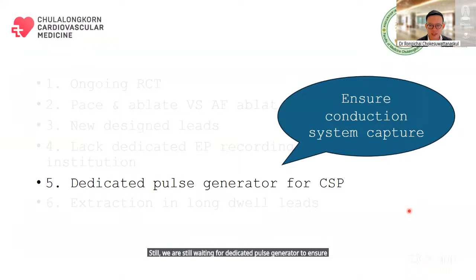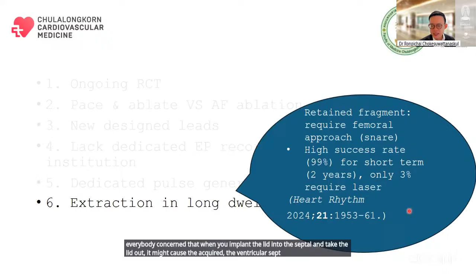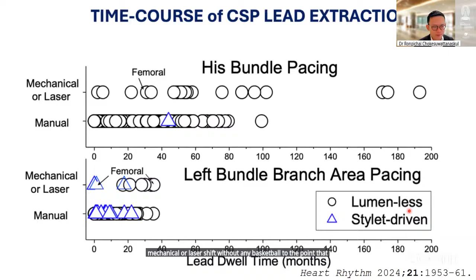And extraction is not that bad either. Everybody is concerned that when you implant the lead into the septum and take the lead out, it might cause a ventricular septal defect, but it's not that bad. We have studies on lead extraction in the CSP with the longest follow-up periods of 2 or 3 years. I know that we are not talking about 10 or 20 years of lead extraction, but so far, with the evidence at 2 or 3 years, it's fine to pull the lead out with some assistance from a mechanical or laser sheath, without any bad sequelae to the point that we need an operation to fix something like a hole in the septum.